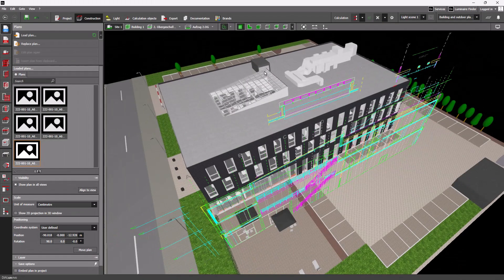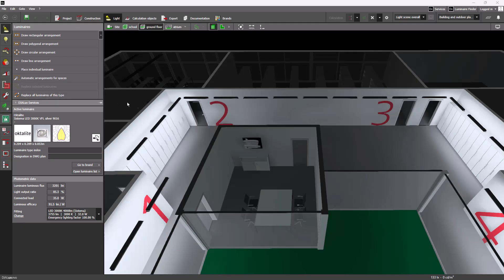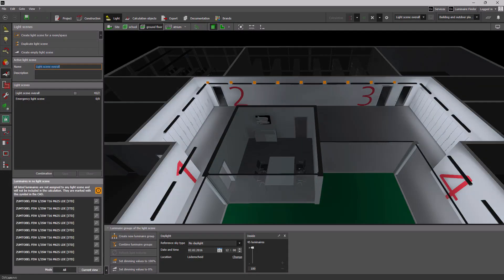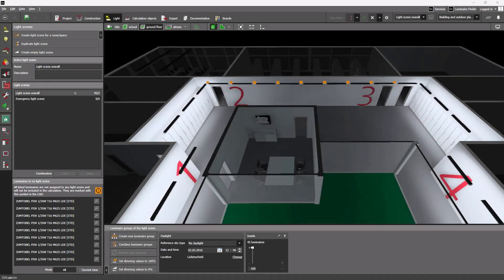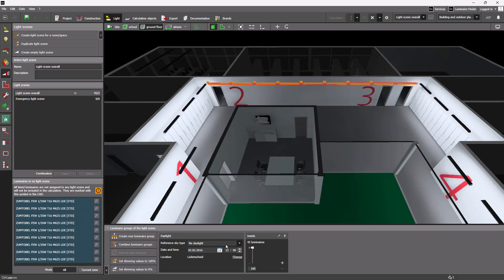Now let's talk about some new functions. We implemented a support feature for identifying luminaires that are not linked to a light scene. Normally, DIALux ensures that luminaires are consistently assigned to at least one light scene. However, during the process of working with light scenes, some luminaires may become unassigned. These unassigned luminaires, which appear black, are excluded from calculations since DIALux calculates light scenes individually. The new support feature now lists these unassigned luminaires, allowing users to select them from the list and view them in the CAD. Users can then add them to an existing light scene or create a new light scene incorporating these luminaires.